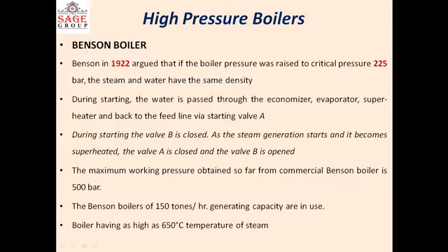So the second is the Benson boiler. Because there were some difficulties arising in the Lamont boiler, and that is the attachment of the steam bubbles on the surface of the inner tubes of the boiler. So in 1922, Benson argued that if the boiler pressure was raised to the critical pressure, that is up to 225 bar, at this pressure the steam and the water both will have the same density.